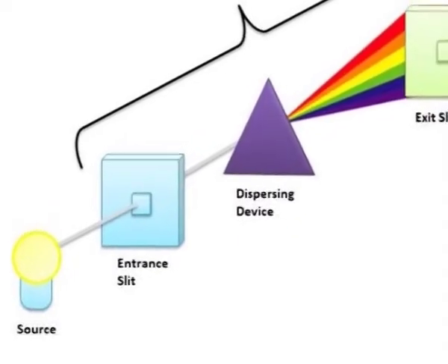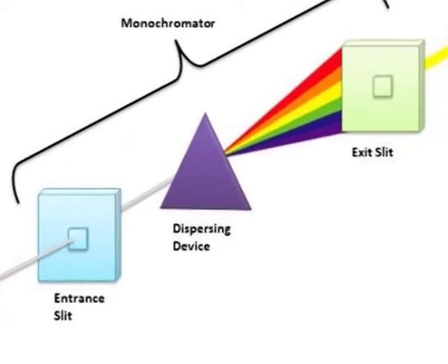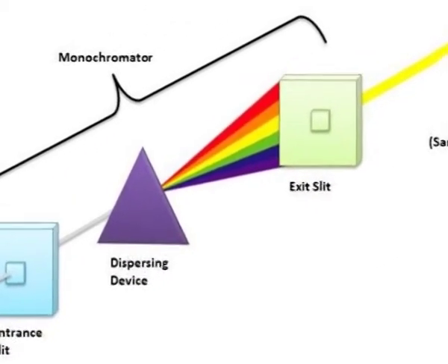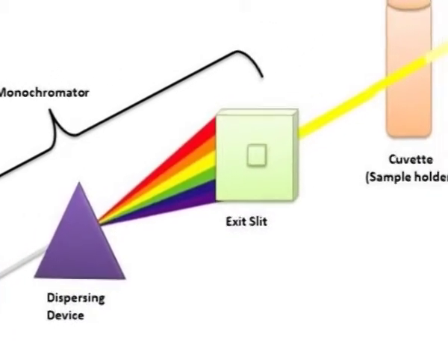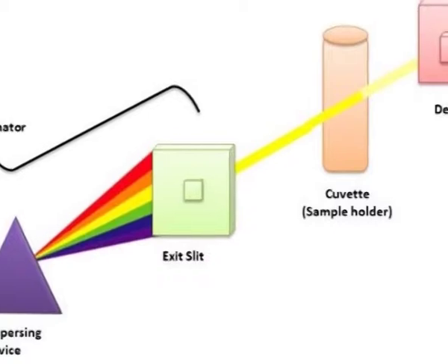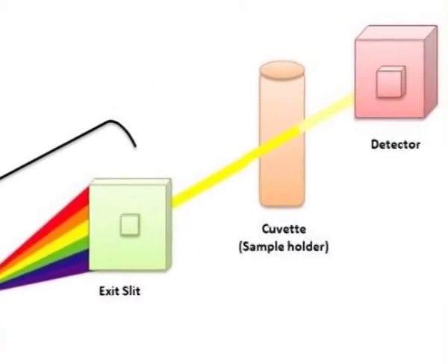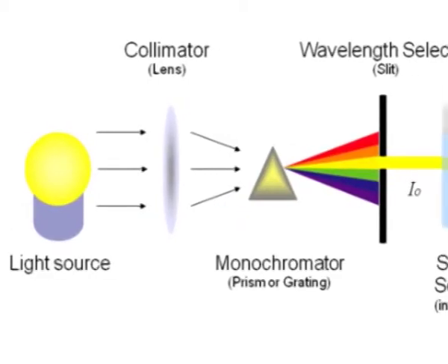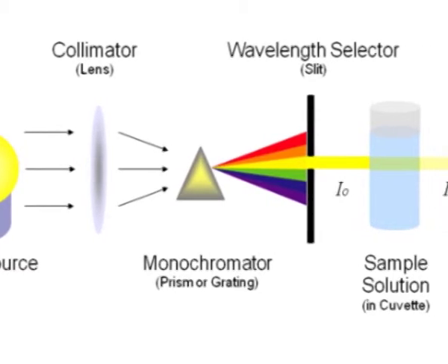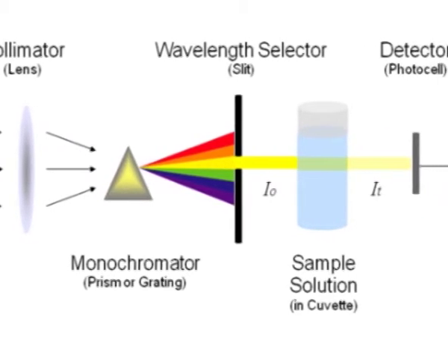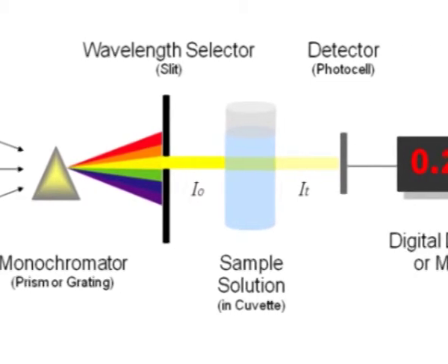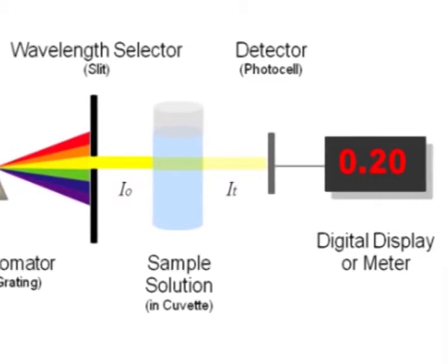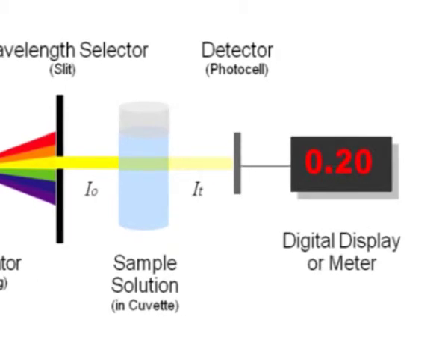The spectrophotometer technique is to measure light intensity as a function of wavelength. It does this by diffracting the light beam into a spectrum of wavelengths, detecting the intensities with a charge coupled device, and displaying the results as a graph on the detector and then the display device. The basic parts of a spectrophotometer are a light source, a holder for the sample, a diffraction grating in a monochromator or a prism to separate the different wavelengths of light, and a detector.